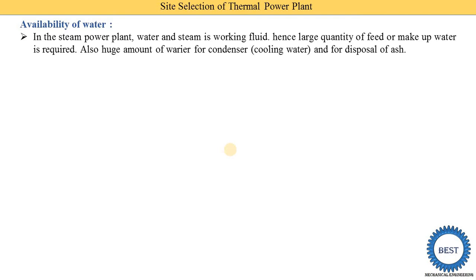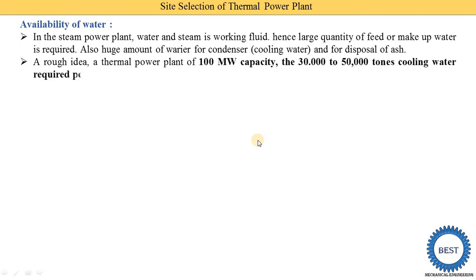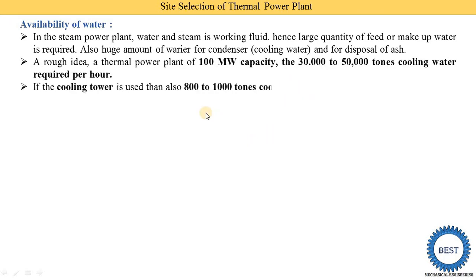A huge amount of water is required for condensers and for disposal of ash. A thermal power plant of 100 megawatt capacity requires 30,000 to 50,000 tons of cooling water per hour. If a cooling tower is used — meaning a closed system for cooling water — then 800 to 1000 tons of cooling water are required per hour. So if we use a cooling tower, the requirement is reduced to 800 to 1000 tons. The makeup water required to compensate for loss of feed water is also 10 to 15 tons per hour.